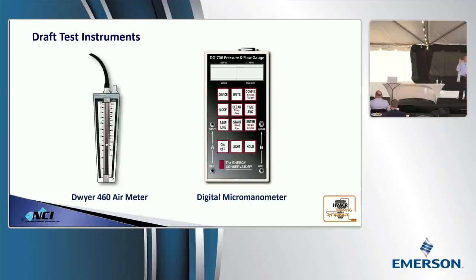And here's the reason. It's visual. There is a small white ball that moves up and down in that gauge, and it visually represents the building breathing. It represents draft. And typically with draft, we're looking for a negative 0.01 to 0.02 inches of water column draft. That's based on the pressure drop needs of the heat exchanger in most instances. Now, there's other formulas that'll teach you how to do it based off of outdoor temperature and pascals and all that, and if you want to do all that, knock yourselves out. I'm just going to tell you based off the pressure drop of the heat exchanger.